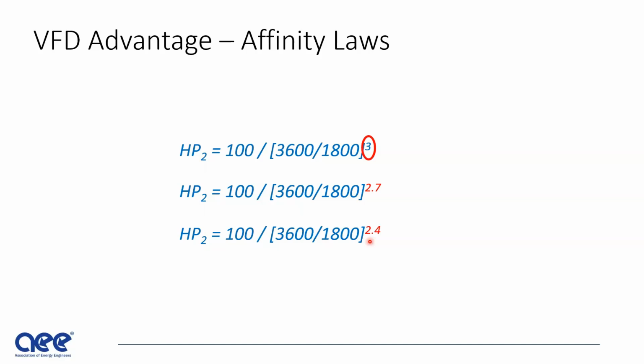If you've got a water pump and a gate valve on that water pump, and that gate valve is used to modulate the volume of water, that's counteracting the benefit of the VFD on the motor, on the pump, and you're nowhere near 2.7. You're probably closer to 2.4, 2.3, or 2.1. So you have to be careful on the exponent here. Rule of thumb, use 2.7, but you have to look at what's attached to that shaft to really know where you need to be.